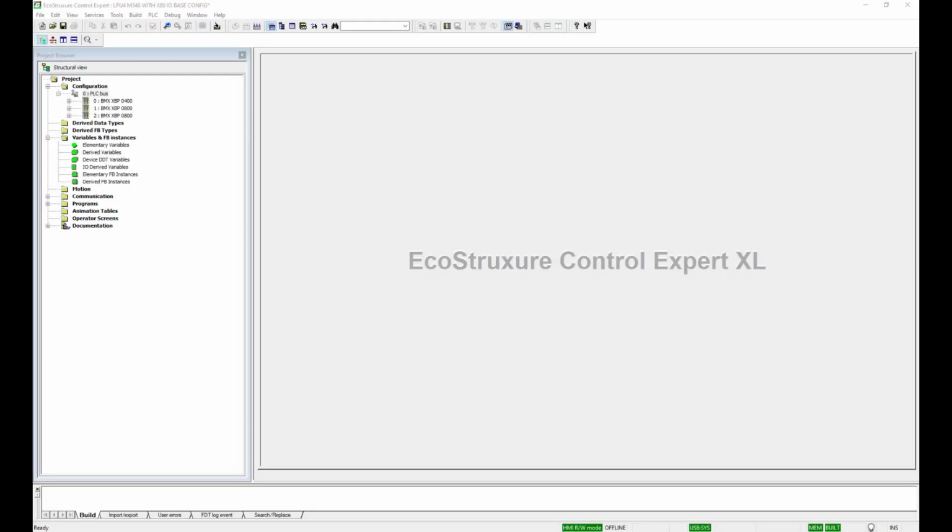The final step is to create a new Control Expert program with a M340 processor, a NOE module, and the correct X80 IO modules for replacing the Quantum IO modules. Rather than use a M340 with Ethernet, I chose the BMX P34-2000 with a NOE module because the NOE provides IO scanning, NTP, as well as other capabilities not provided on the BMX P34-2020. Using the spreadsheet created earlier, do the following.